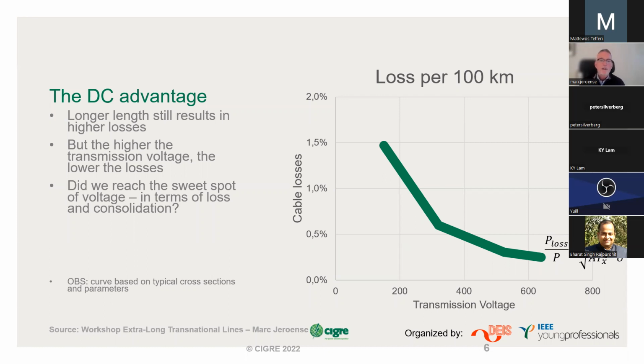This graph on the right shows, in an easy way, how the cable losses relate to the power you want to transmit, as a percentage. It's an inverse power curve—one over U. It goes down quickly, but every time you want to decrease the cable losses by another factor of 2, you have to increase the voltage by a factor of 2. It becomes obviously more difficult the higher you go in voltage.